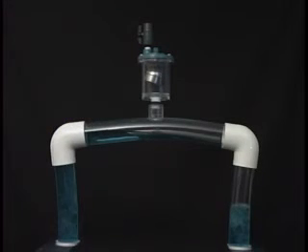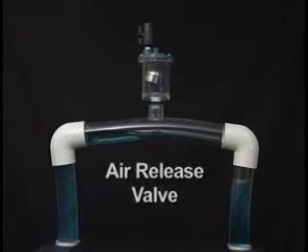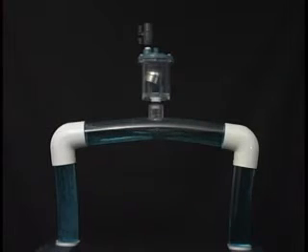Here's a sample pipeline with an air release valve at the high point. An air release valve, sometimes referred to as a small orifice valve, will continuously release accumulated air during system operation. As air from the pipeline enters the valve, it displaces the water, allowing the float to drop. The air is then released into the atmosphere through a small orifice.